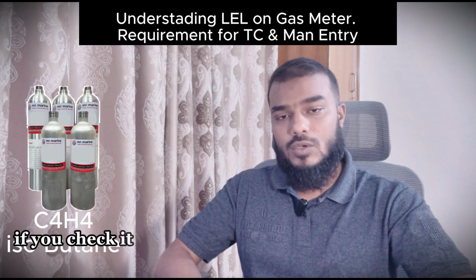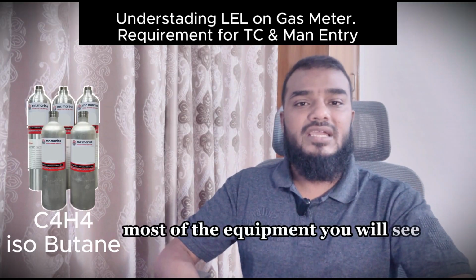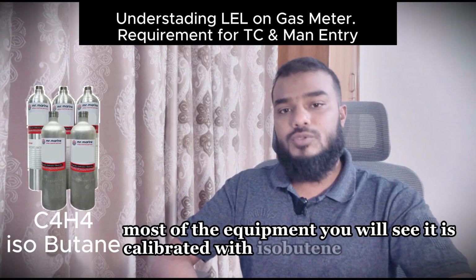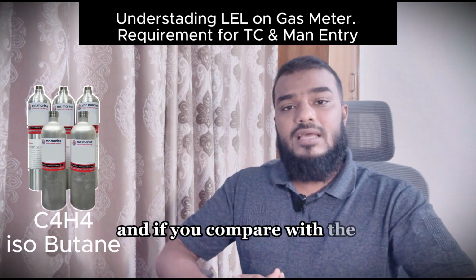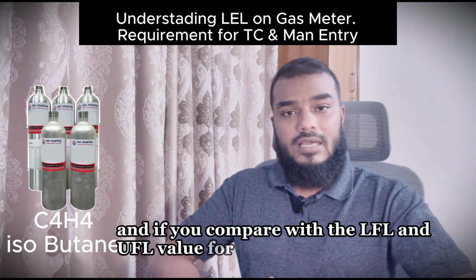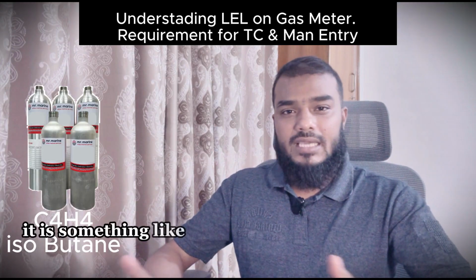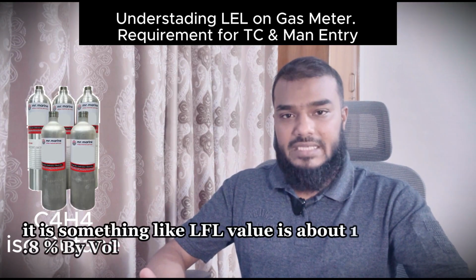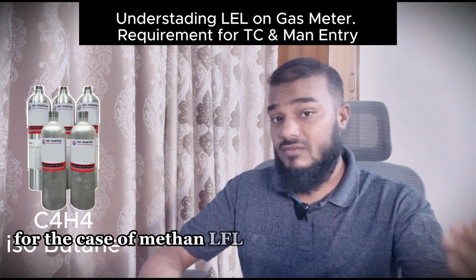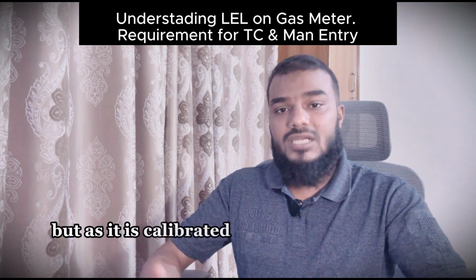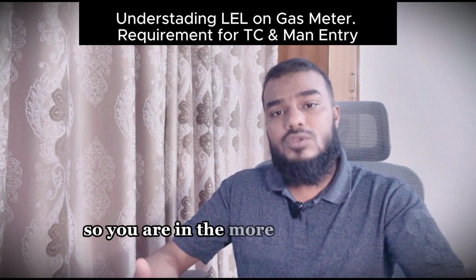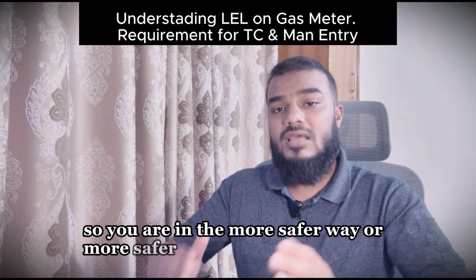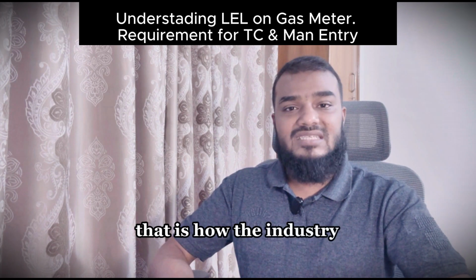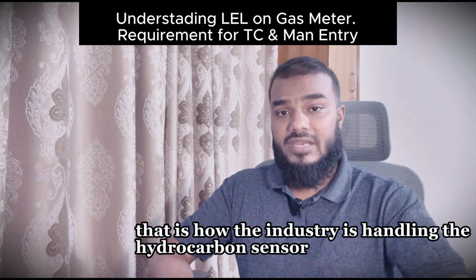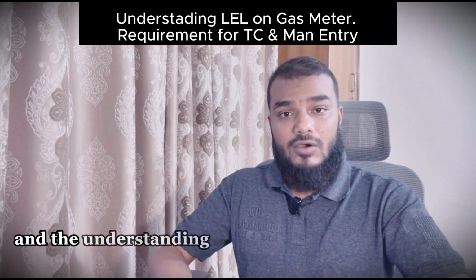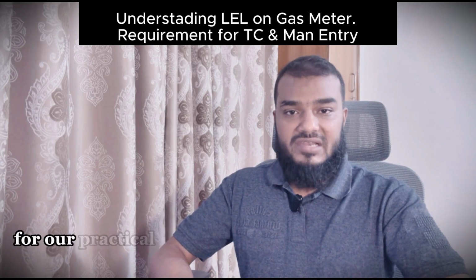Now the question may come: which gas is used for calibrating this hydrocarbon sensor? If you check closely, most of the equipment is calibrated with isobutane. The LFL value for isobutane is about 1.8, whereas for methane the LFL value is 5. But as it is calibrated with isobutane, you are on the safer side. That is how the industry handles the hydrocarbon sensor reading for our practical purposes.